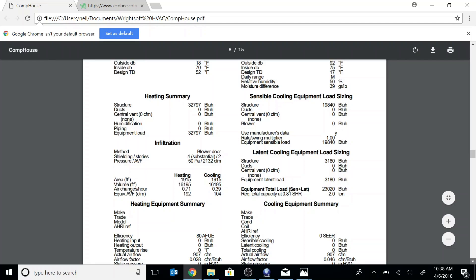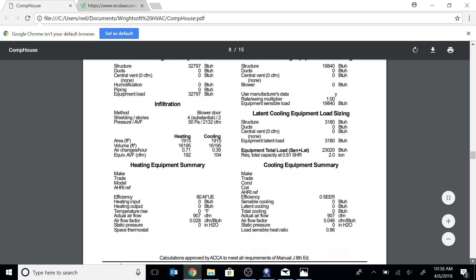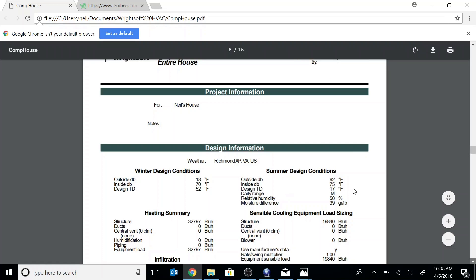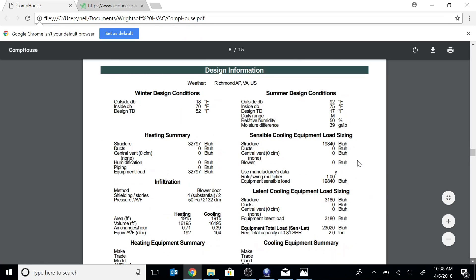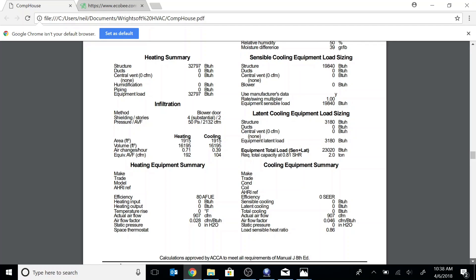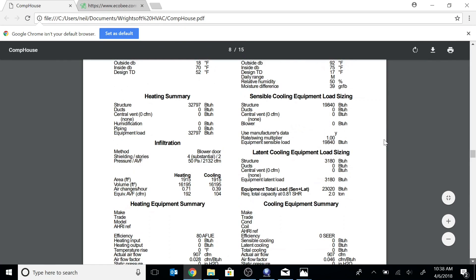Here's the square footage: 1915. And for cooling: 92 degrees outside, 75 inside. You can see that the latent is 3180 and the sensible is 19,840 — a total of 23,020. Again, check the expanded performance data on equipment, and a two ton unit will handle both the latent and the sensible at 92 degrees outside and 75 degrees inside.